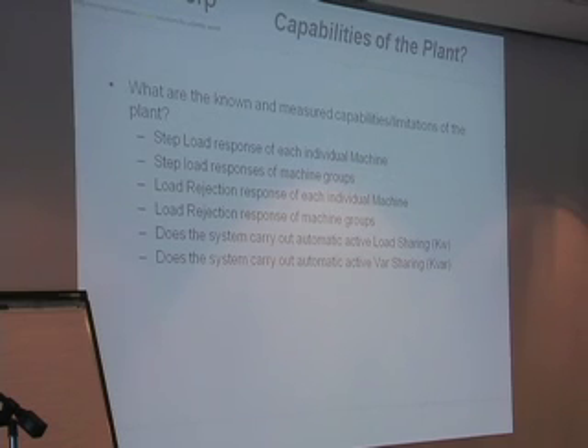Active kilowatt and kVAR sharing these days are pretty standard in the controllers you can buy, and without that, especially with the VARs, you might be making energy in one machine and feeding it to the other, just heating up all the cables and burning fuel. So that's pretty standard now with the controls you can buy for the gen sets.